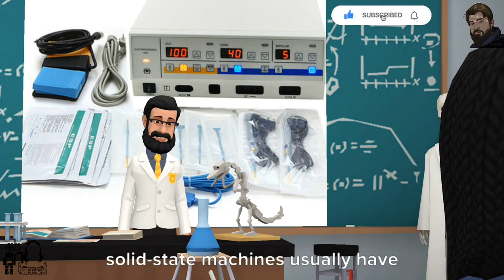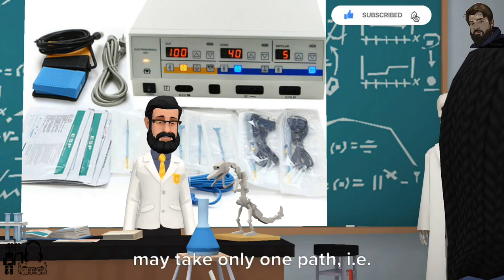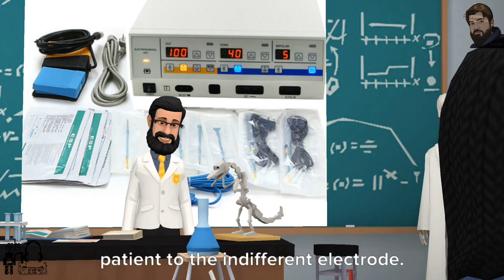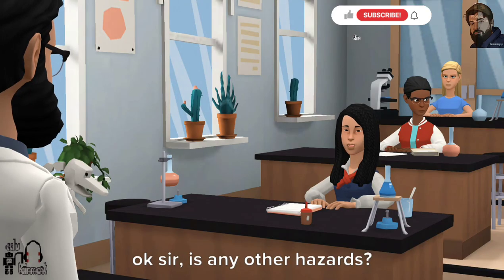Modern solid state machines usually have RF isolated patient circuits. This implies that ideally RF current may take only one path, that is from active electrode through the patient to the indifferent electrode.